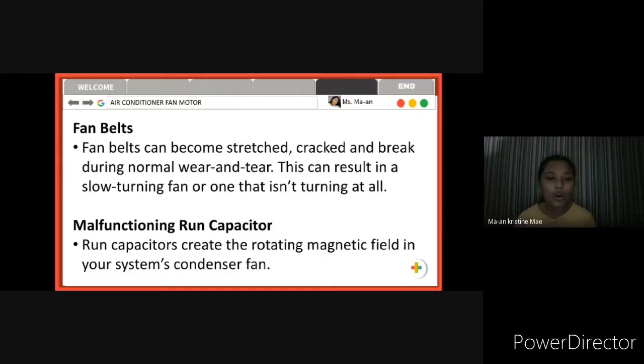The next one is the fan belt. It is said here that the fan belt can be stretched, cracked, and broken during normal wear and tear. When the fan belt is broken, this can result in the fan not working at all. You really need to replace the fan belt immediately, because if you can't replace it, the fan belt can break it. The third one is malfunction of the run capacitor. The run capacitor creates the rotating magnetic field in the system of the condenser fan. So if the capacitor does not work, it will probably cause the fan to slow down or overheat. Next po.